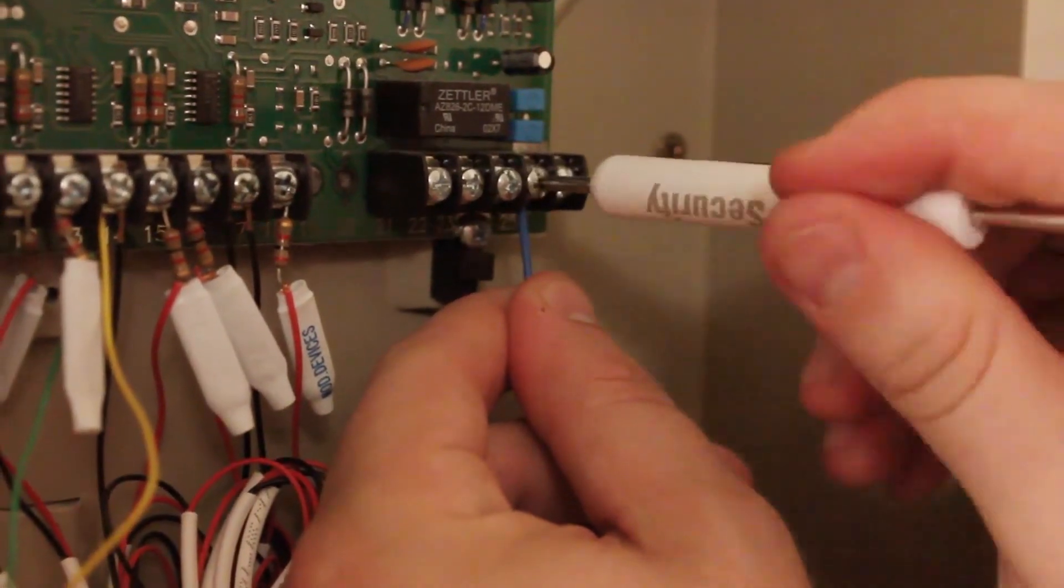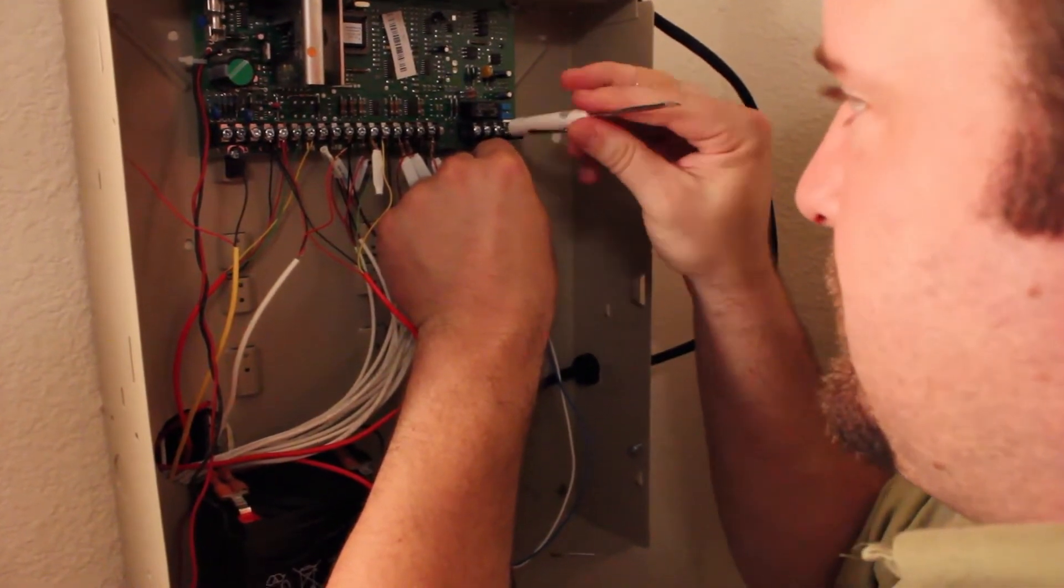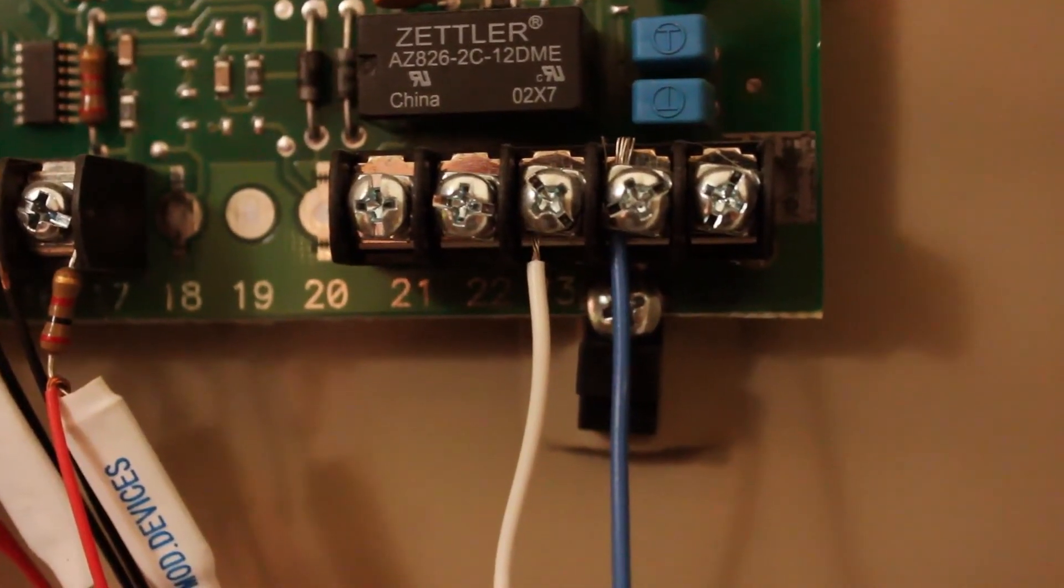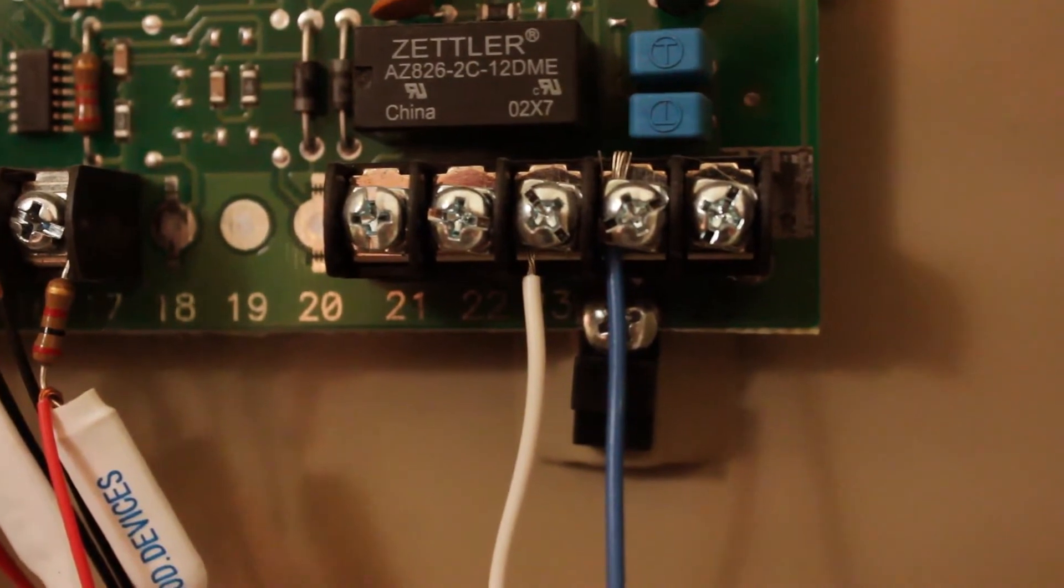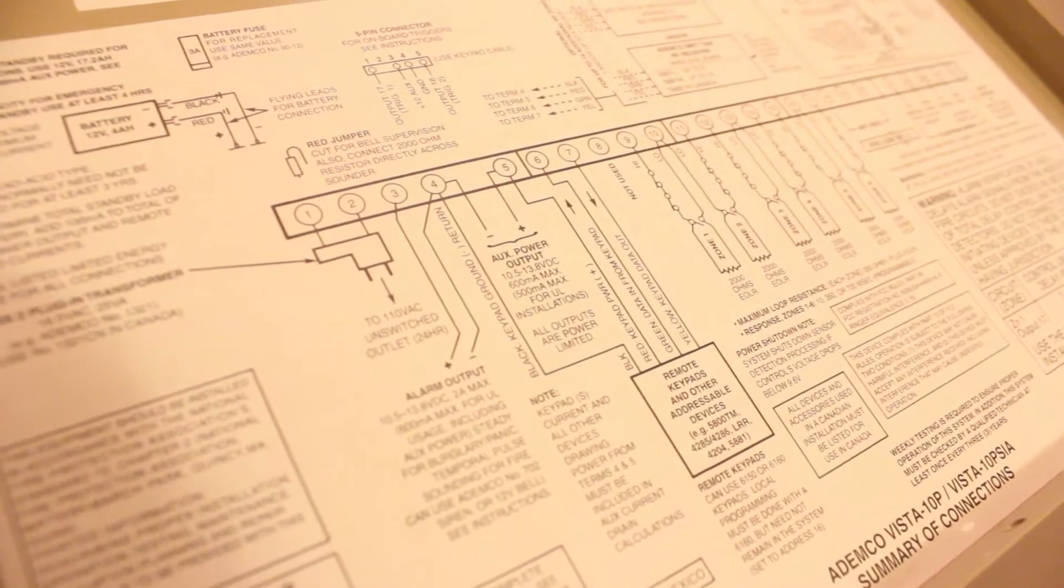Insert the blue and white wires from the conversion device into the tip and ring pins. It doesn't matter which color wire goes where; there is no polarity. Some panels can have different pin arrangements, make sure to consult the schematic.